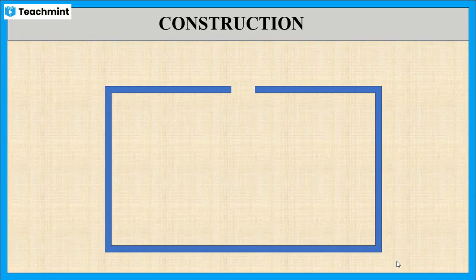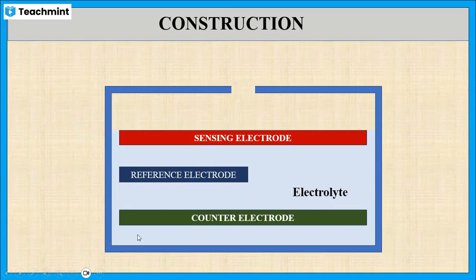Now let us see the assembly of electrochemical sensors. Generally, the electrochemical sensor contains a container filled with electrolyte, which is immersed in three electrodes: sensing electrode, reference electrode, and counter electrode.